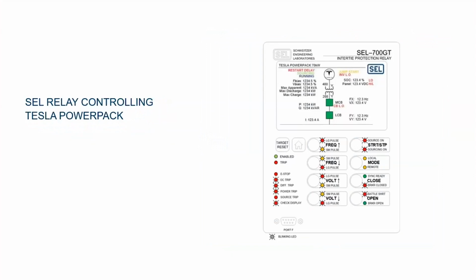This is an example of how we use a relay to control an inverter-based resource, or an IBR, with a single SEL relay. Here you see the HMI that historically required a Windows computer is now an embedded graphic that you can program. You now have push buttons for dispatching your DER, the raise and the lower of frequency and voltage, power and reactive power, opening and closing breakers. We'll talk more about the local and remote button, very important button. Annunciation of major alarms on the left LEDs. And furthermore, if you have a check display light flashing, you go see lower tier alarms.